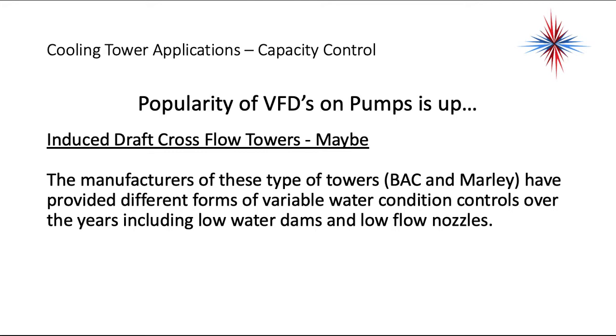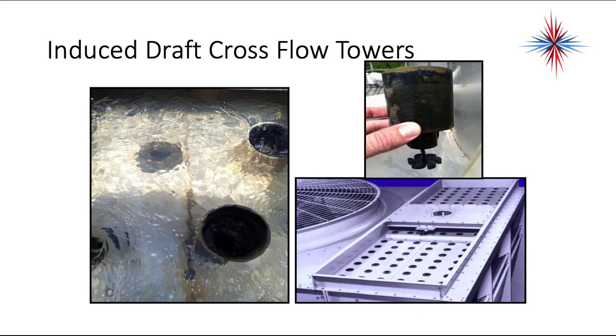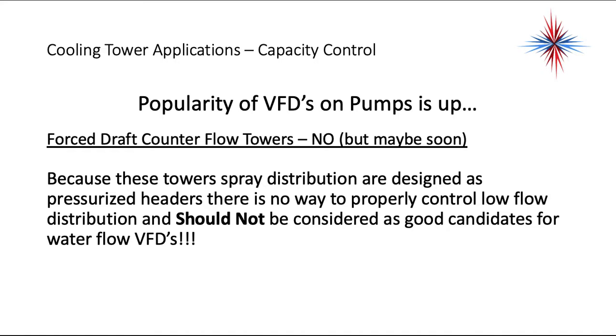There is some popularity of variable frequency drives on pumps. In induced draft cross-flow towers, manufacturers such as BAC and Marley have provided different forms of variable water condition controls over the years, including low water dams and low flow nozzles. For forced draft counter-flow towers, VFDs on pumps are not yet used, but possibly soon. Because these towers' spray distribution systems are designed as pressurized headers, there's no way to properly control low flow rates and they should not be considered good candidates for water flow VFDs.